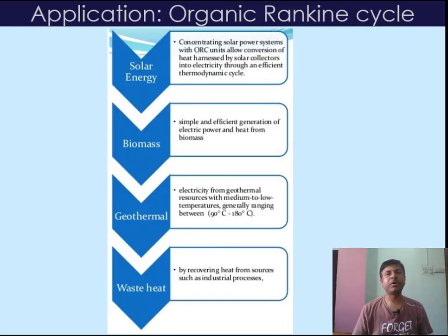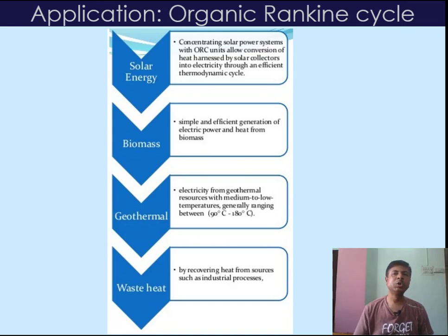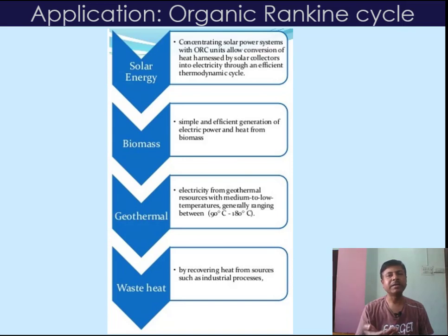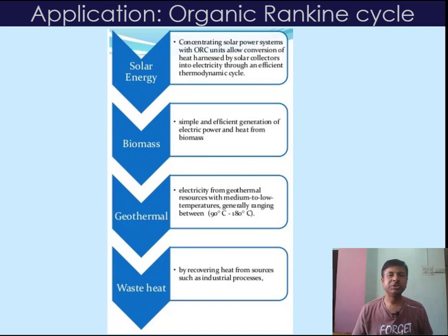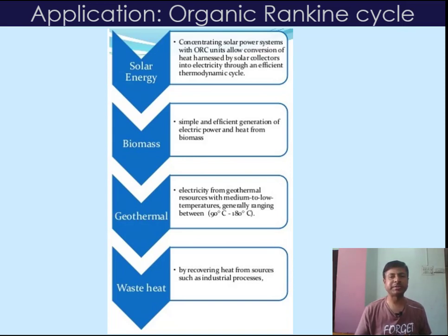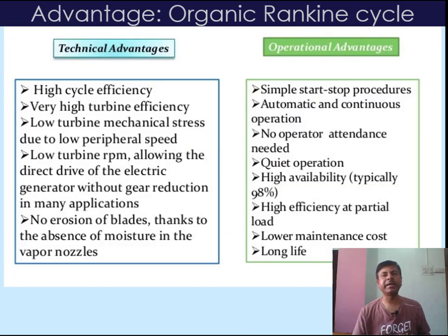Coming to the applications of Organic Rankine Cycle: for solar energy, concentrating solar power systems with ORC units allow conversion of heat harnessed by solar collectors into electricity through an efficient thermodynamic cycle. In biomass, it enables simple and efficient generation of electric power and heat. In the geothermal sector, electricity is generated from geothermal resources with medium to low temperatures, generally ranging between 90°C to 180°C. In waste heat recovery systems, heat is recovered from sources such as industrial processes.